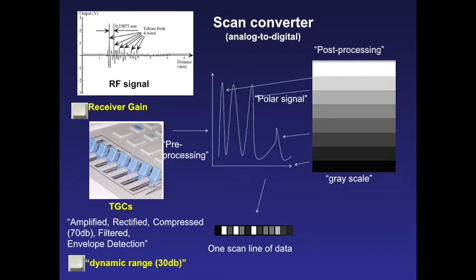Well, you get this polar signal now, and it is represented by one line, one scan line of gray. So instead of these peaks and valleys, you have blacks and whites, and those blacks and whites create one scan line of data, and that one scan line of data is shown on the screen.